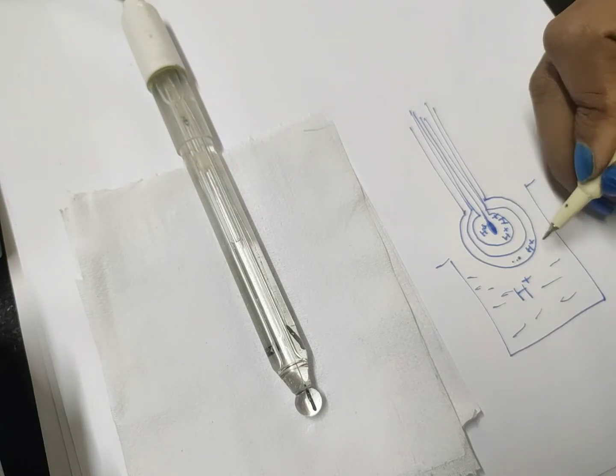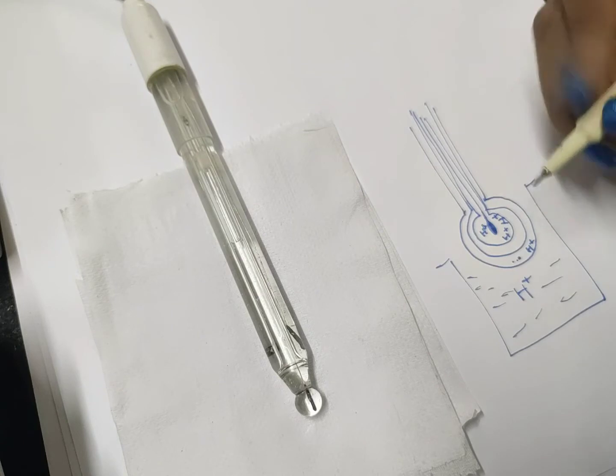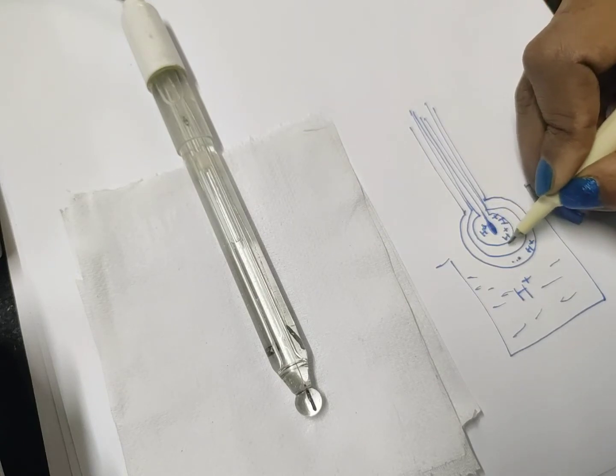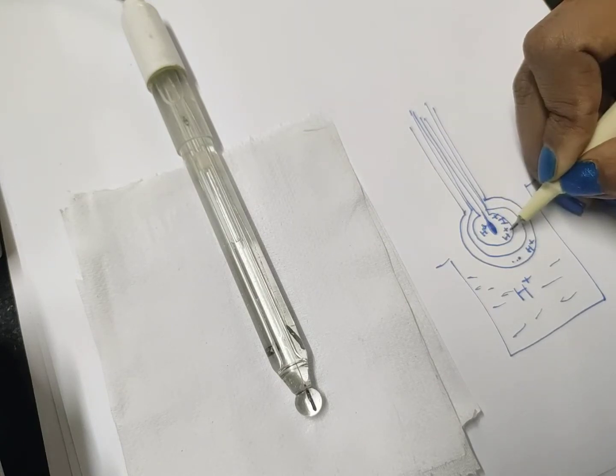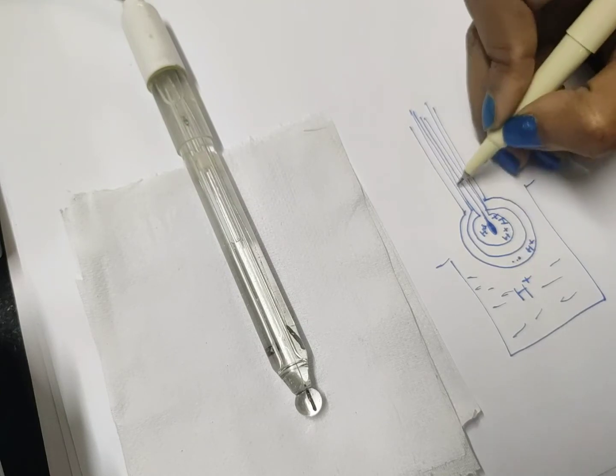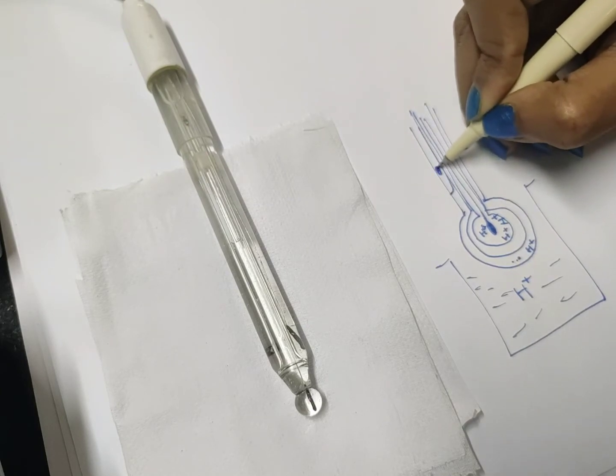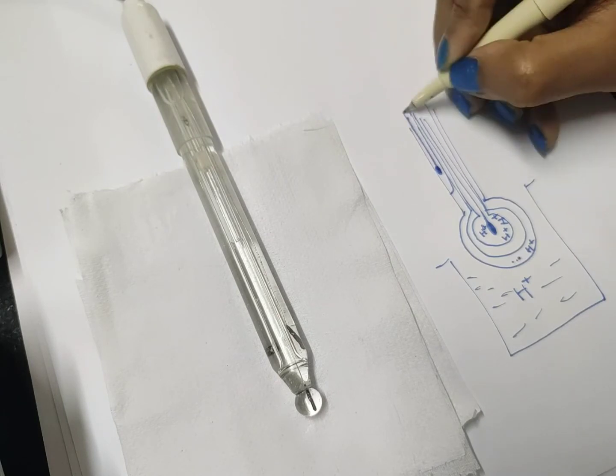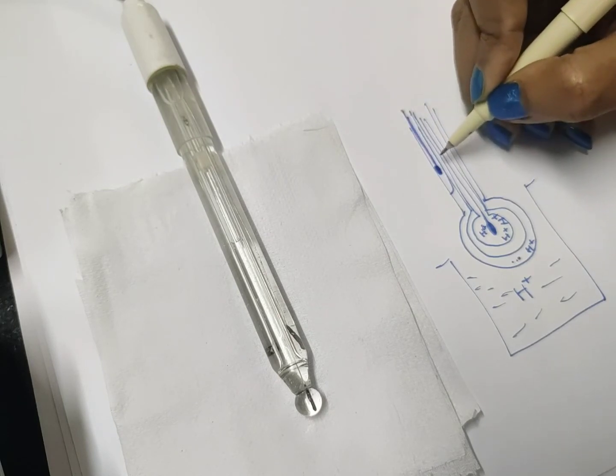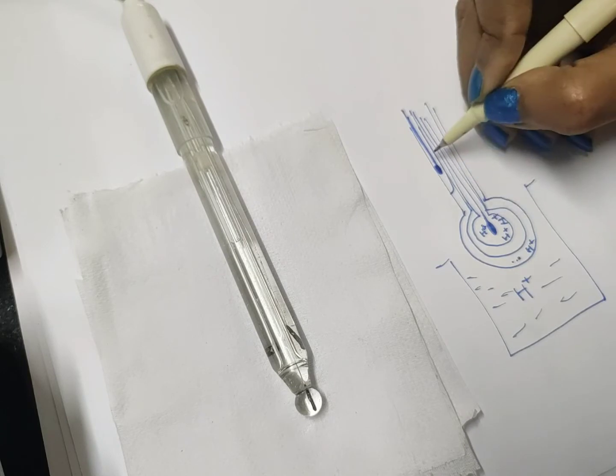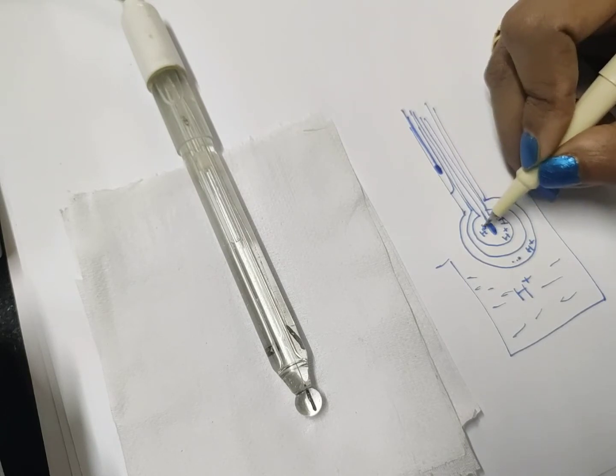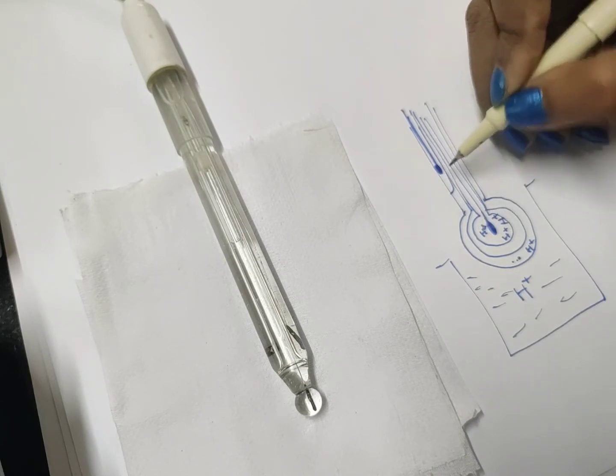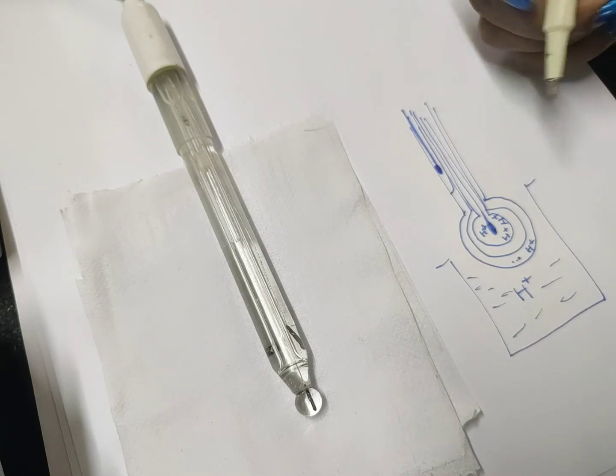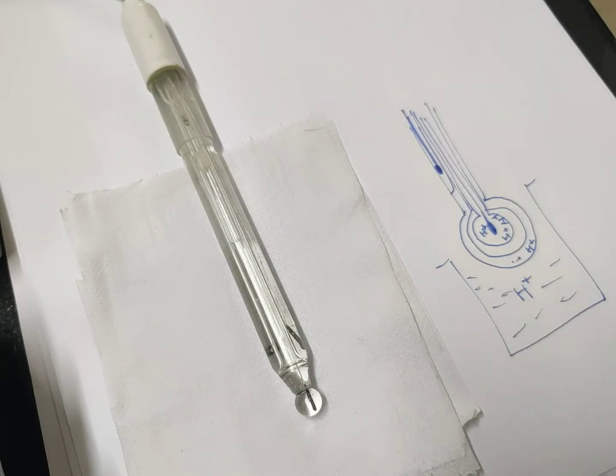Okay, so depending on this the instrument sees. Now first thing is it will see how much is the hydrogen ion, what is the difference of this hydrogen ion concentration in this layer and with the internal solution, and then it will compare with inside that one more electrode that is present, which is called the reference electrode. Then it will see what is the difference of this. So depending on the potential difference of this and this, your pH meter will calculate how much is the pH. Okay, so this is to say how exactly the pH probe works.